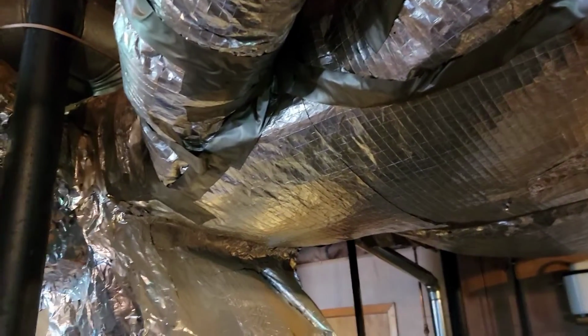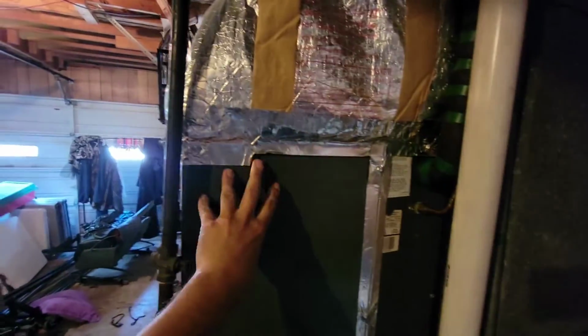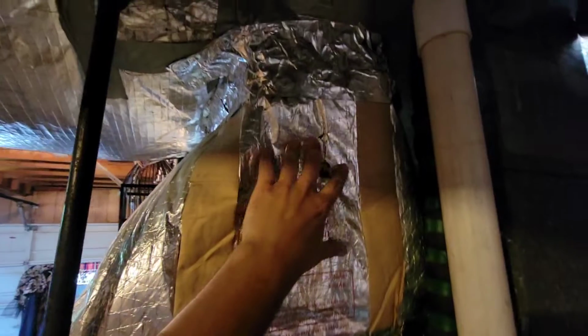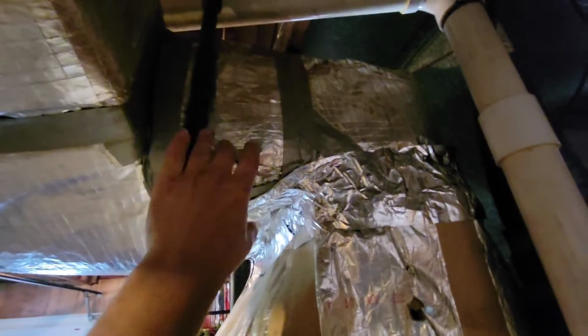This right here is the indoor part. This is the supply trunk. And this right here is the indoor coil. All right, you can see that indoor coil there. But what we see here is, this is the length of the coil. Transition goes up, kind of closes off, hits that hard 90 there, and then you have this size duct, which is 9 by 24. We need to take a look at the Ductulator and check this out because we don't have a lot of air to any of the supply vents.